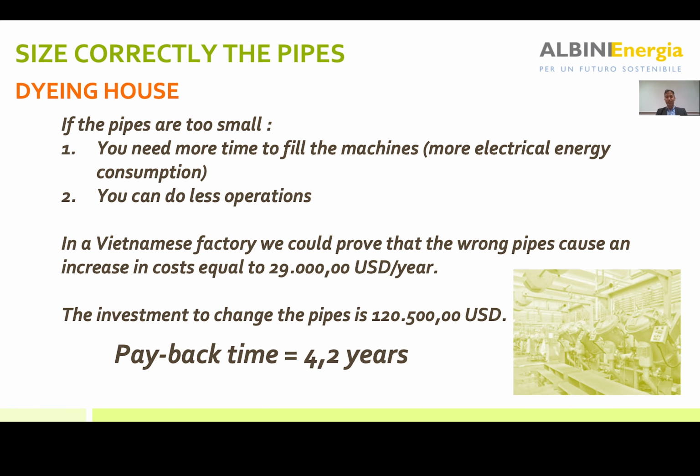Maybe easy to understand, but anyway, I've noted that people didn't care too much about it. I mean, the connection between the big pipes, the manifolds, and your machines. If you put small pipes, especially on the water lines, hot water, cold water lines, if you put small pipes on the steam, you are going to need more time to fill the machine, to warm the machine, and to reduce the temperature inside the machine.